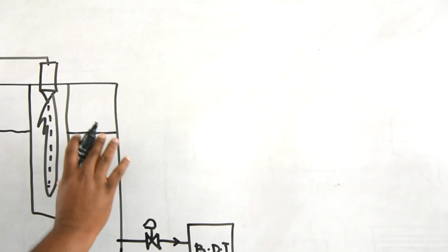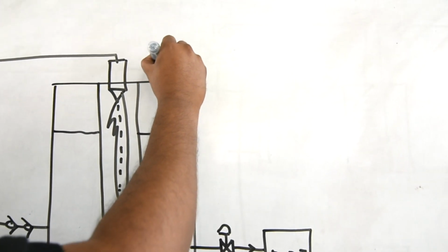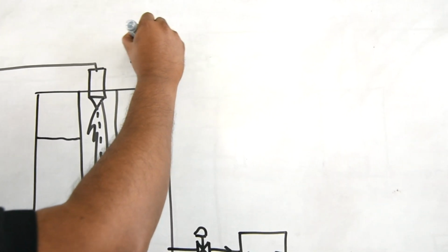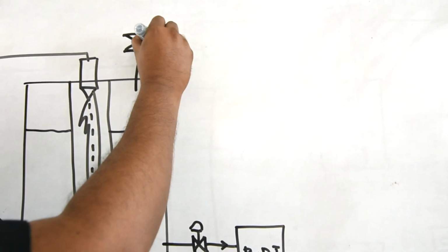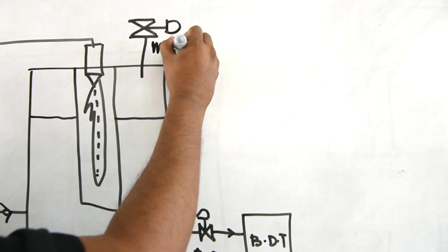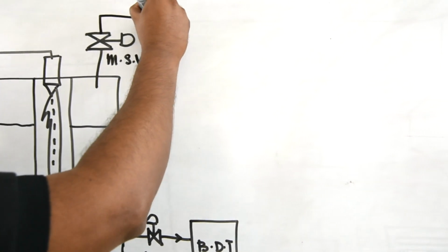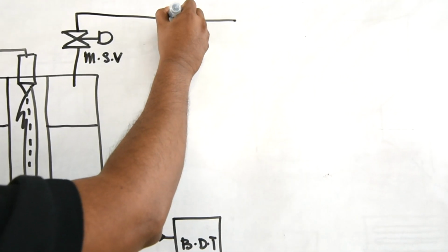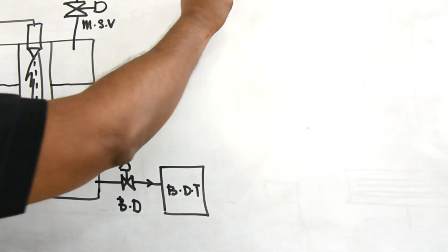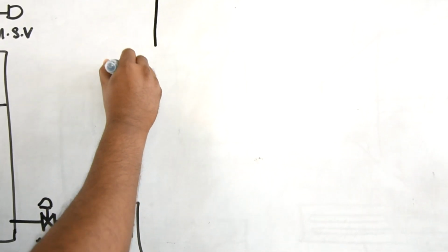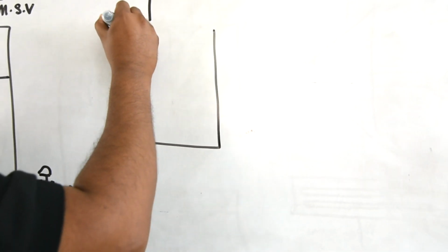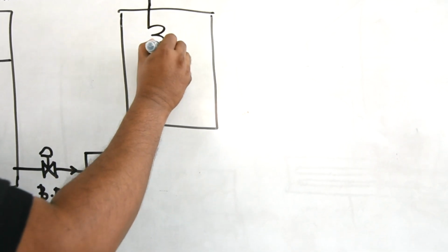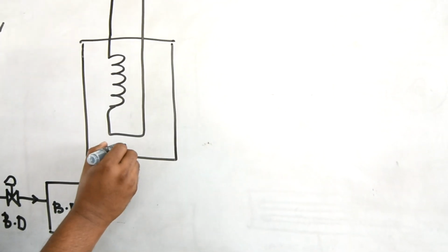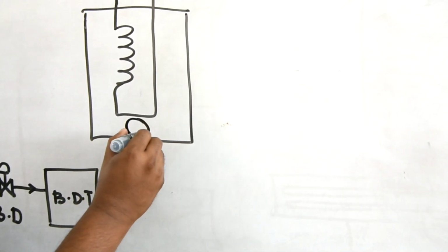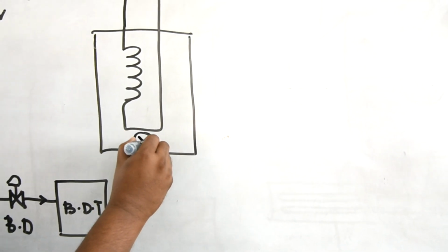Now, once this boiler is pressurized, we have a passage to release the pressure, and we have a main steam valve. And this main steam valve will release saturated steam. And this saturated steam will be going into another component which is called the superheater. We have a superheater, and this superheater has a coil and it will produce superheated steam. And individually this superheater is fired by a burner supplied from the same fuel tank. So this is your burner.